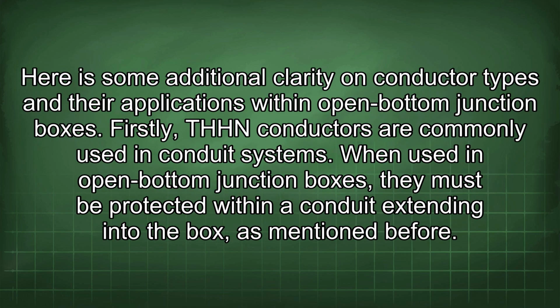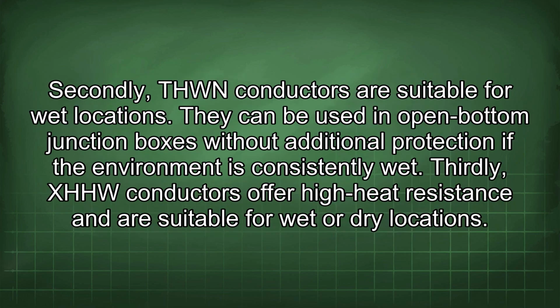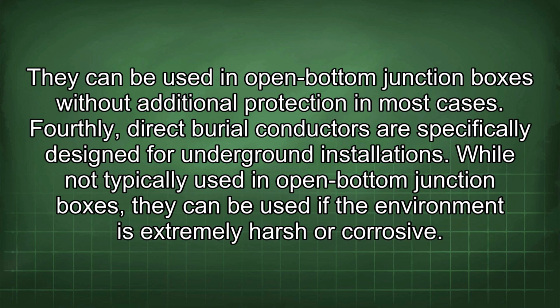Here is some additional clarity on conductor types and their applications within open-bottom junction boxes. Firstly, THHN conductors are commonly used in conduit systems. When used in open-bottom junction boxes, they must be protected within a conduit extending into the box, as mentioned before. Secondly, THWN conductors are suitable for wet locations. They can be used in open-bottom junction boxes without additional protection if the environment is consistently wet. Thirdly, XHHW conductors offer high heat resistance and are suitable for wet or dry locations. They can be used in open-bottom junction boxes without additional protection in most cases. Fourthly, direct burial conductors are specifically designed for underground installations. While not typically used in open-bottom junction boxes, they can be used if the environment is extremely harsh or corrosive.